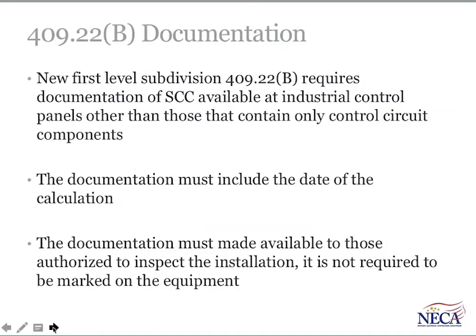Article 409 covers industrial control panels. A small change here: these things require a short circuit current rating to make sure they're not used on a short circuit that exceeds their rating. New requirements are for documentation that documents the amount of available short circuit current at the industrial control panel and the date of the calculation, and that documentation must be made available to those authorized to inspect the installation. Obviously, verifying that the industrial control panel has a rating and is used within its rating is important for the approval process for inspection authorities.